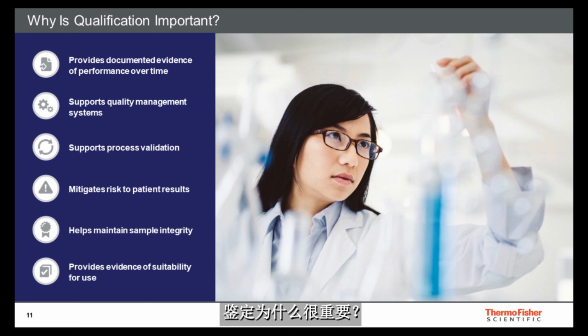Why are qualifications important? Qualifications are important as documented evidence of performance over time. As we have established in the previous slide, qualifications are a periodic and ongoing necessity. Qualifications support quality management systems, process validation, mitigate risk to results, provide sample integrity, and provide evidence of suitability for use or intended use.